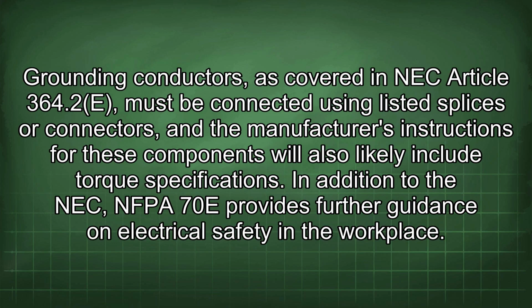Grounding conductors, as covered in NEC Article 364.2(E), must be connected using listed splices or connectors, and the manufacturer's instructions for these components will also likely include torque specifications. In addition to the NEC, NFPA 70E provides further guidance on electrical safety in the workplace.